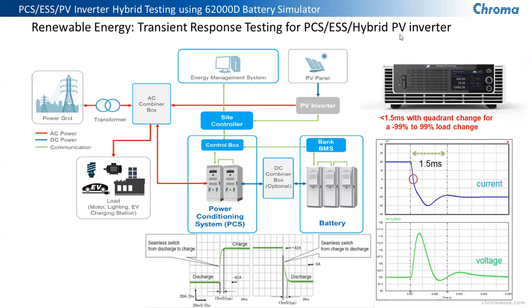Renewable energy. When you're talking about renewable energy, more and more renewable energy sources are including some type of energy storage with it. The reason for that, of course, is a typical solar array system or wind generator will have some erratic operation. It's not a nice continuous conversion of power and output of power back to the grid. So by having energy storage incorporated with it, it gives you a more stable type of energy coming from your renewable energy system. And that's controlled through a PCS, which is basically a power conversion or power control system.